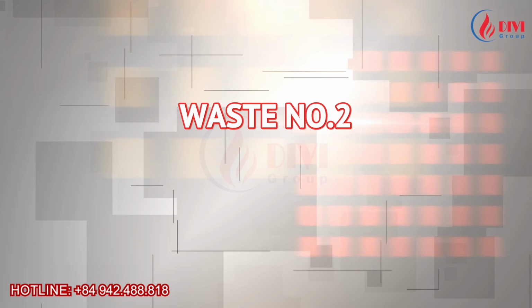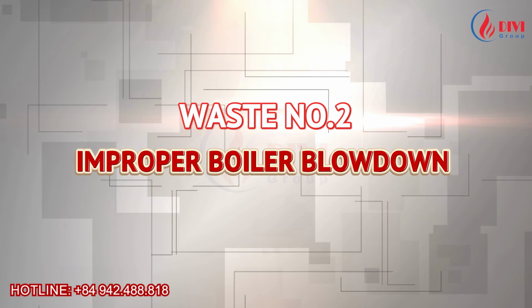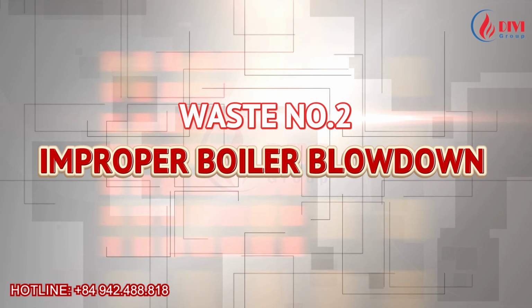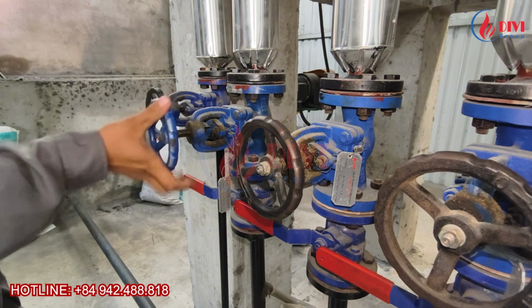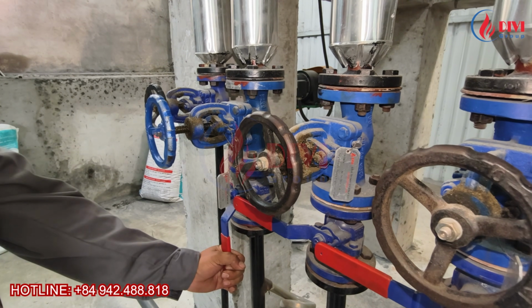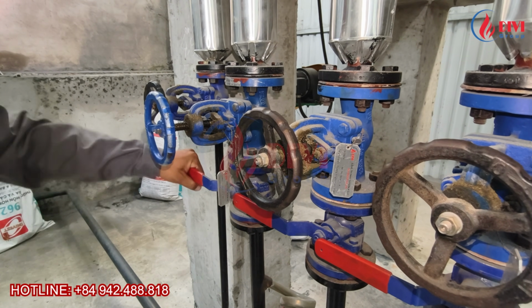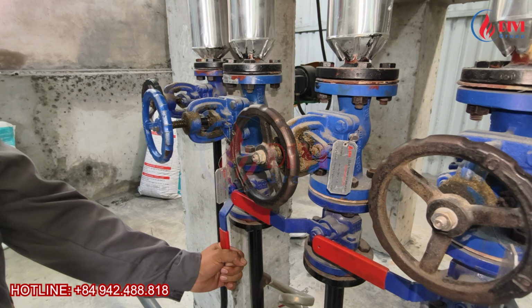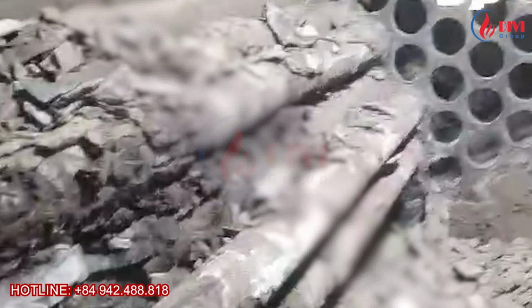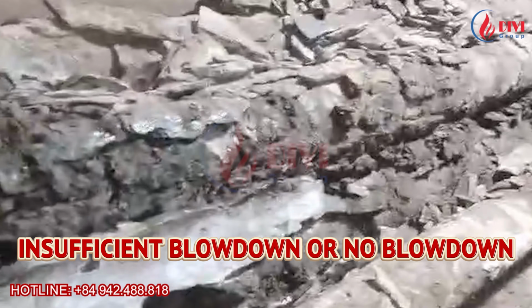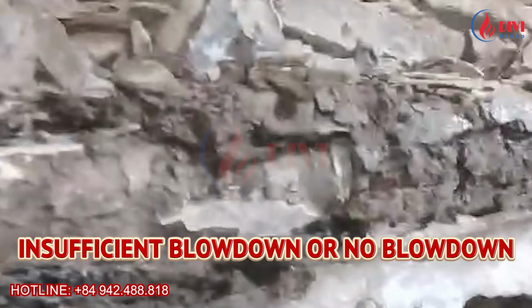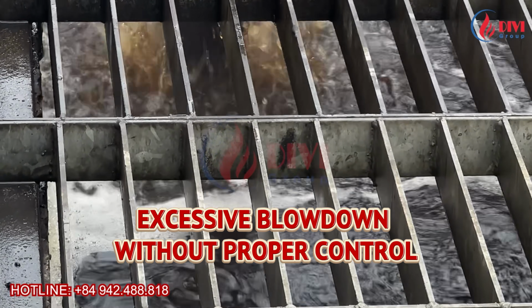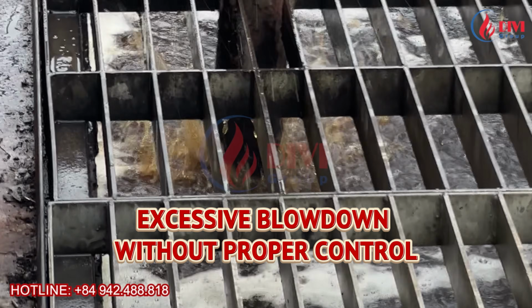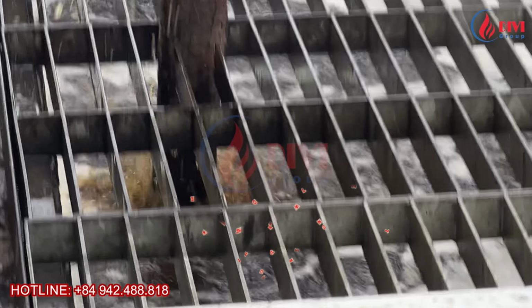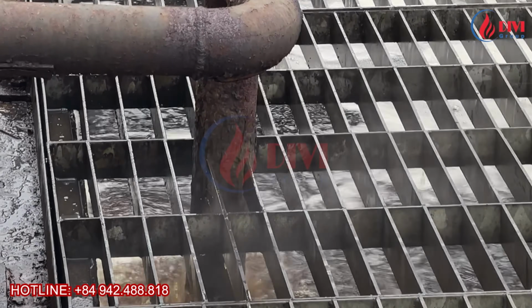Waste number 2, improper boiler blowdown. In a boiler system, blowdown is essential for removing scale and impurities from the boiler water. However, many factories fall into 2 extreme situations. The first is insufficient blowdown or no blowdown at all, which causes heavy scale buildup inside the boiler tubes. The second is excessive blowdown without proper control, leading to major heat and water losses. Both situations create serious energy waste.